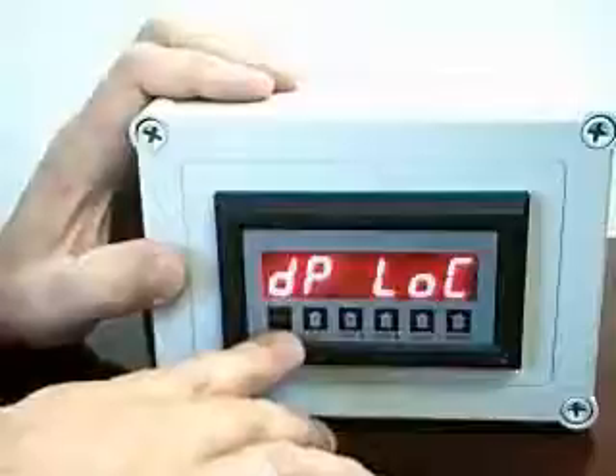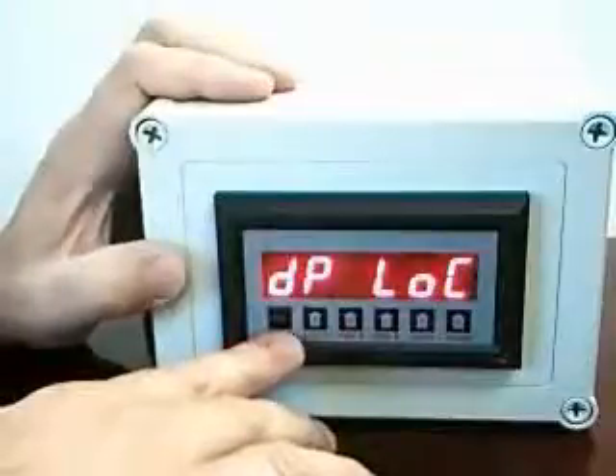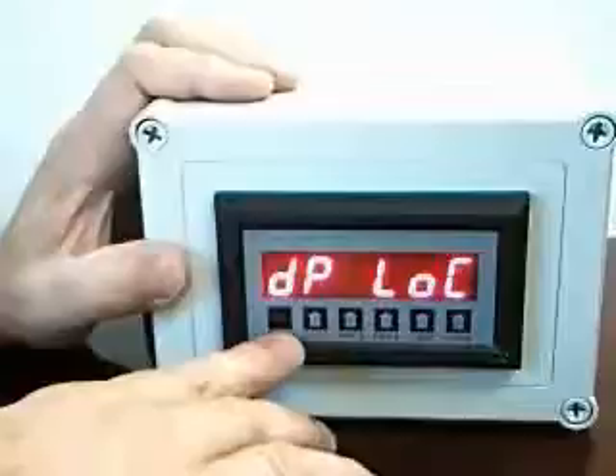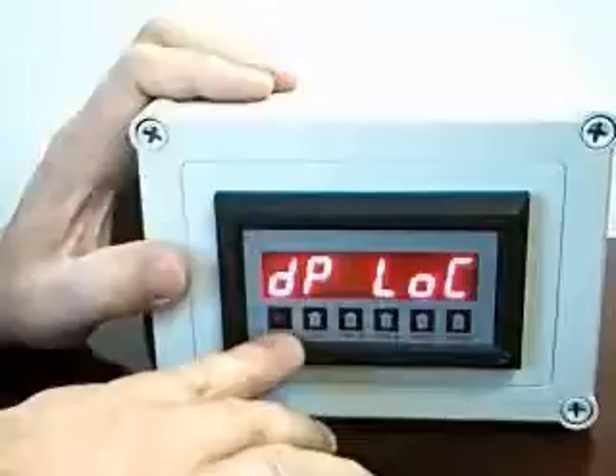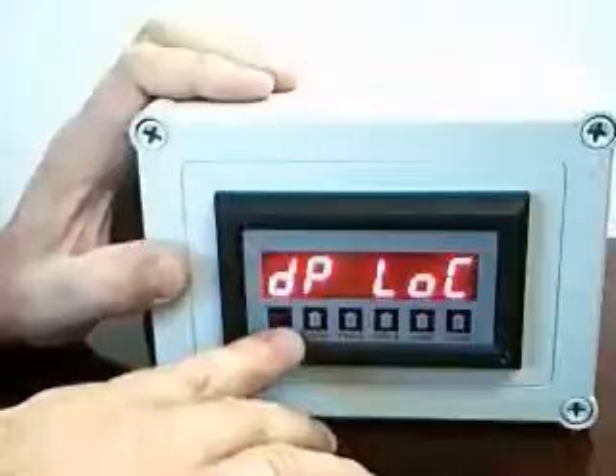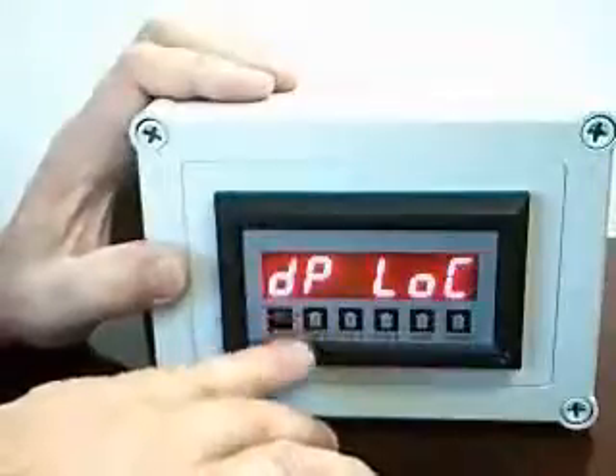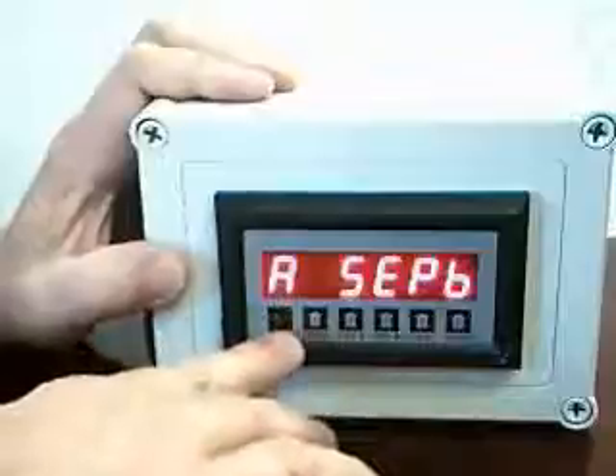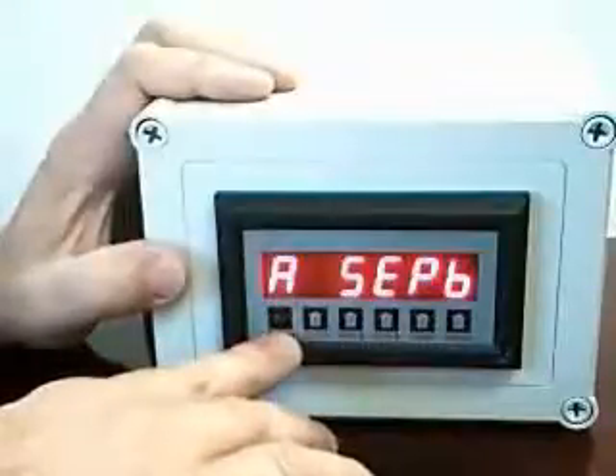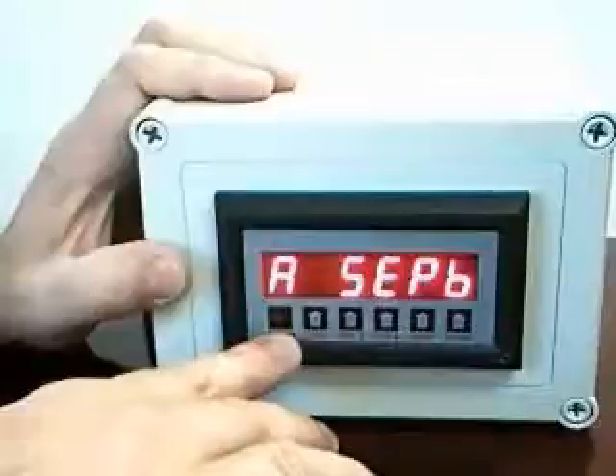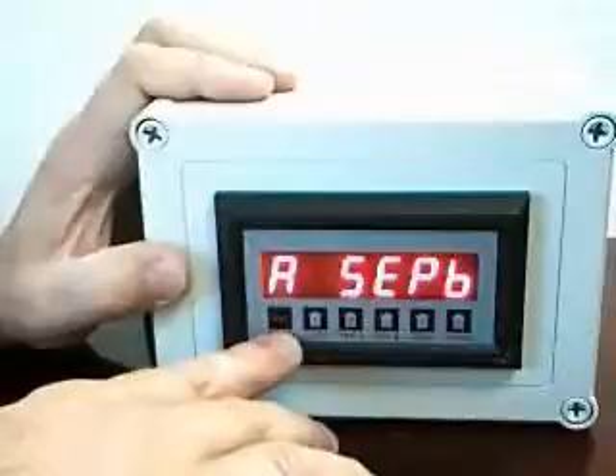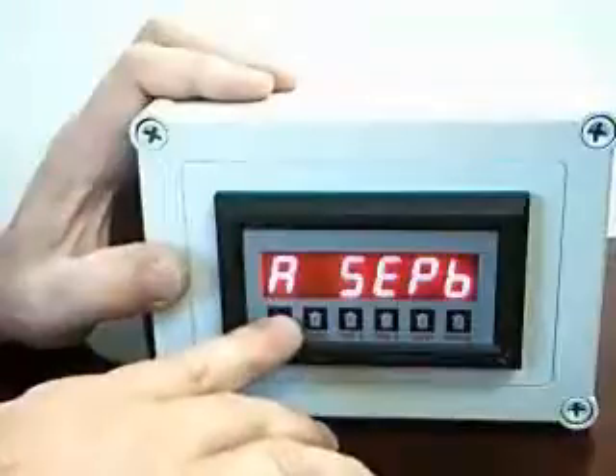I'm then going to go to where it's offering me a selection for the decimal point location to display when it displays the total. I wish to display in whole gallons, so therefore I'm going to have no decimal points illuminated. Hitting Enter again, it now is telling me the mode of operation for this instrument. In this case, it's saying that it wants the A and B channels to be separated. So it's saying A separate B. This is the most common mode for this instrument.